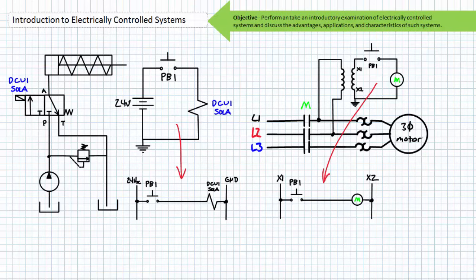Ideally, the power supply and the control transformer establish electrical isolation between the primary and pilot voltages. If one needed to ground the reference output of a control transformer, one customarily does so on the X2 side. This ensures that overcurrent protection devices like fuses and circuit breakers function as intended and ensures that an errant connection to ground does not inadvertently start a hydraulic system or motor.